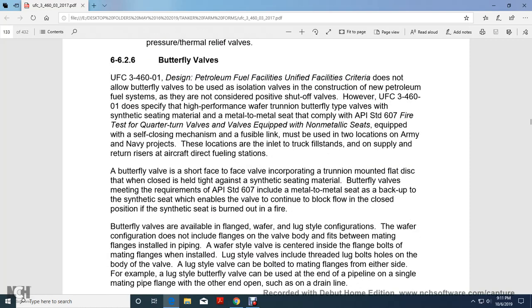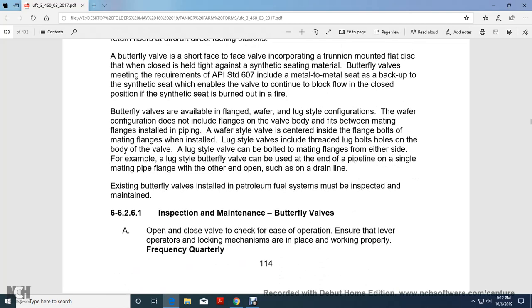626, Butterfly Valves. UFC 3-460-01, Design: Petroleum Fuel Facilities, does not allow butterfly valves to be used as isolation valves in the construction of new petroleum fuel systems, as they are not considered positive shutoff valves. However, UFC 3-460-01 does specify that a high-performance butterfly type valve with synthetic seating material and a metal-to-metal seat, complying with the API Standard 607 fire test, quarter-turn valves equipped with Nonmetallic Seats and a self-closing mechanism with fusible links, must be used at two locations on Army and Navy projects: these locations are the supply and return risers to the aircraft direct fueling stations.